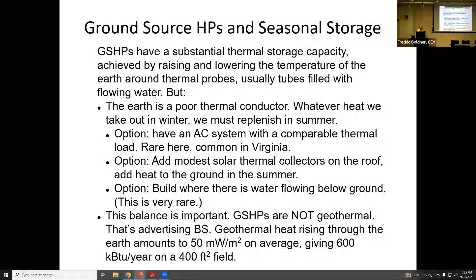Something that's very rare is to have a water table that's actually moving. But if you do, that will bring in enormous amounts of heat and take them away. So that takes care of it. But the balance is important. And one reason it's important is that there is a misnomer that's used quite often when these are called geothermal heat pumps. They are not geothermal. The total amount of heat coming up from geothermal heat is 50 milliwatts per square meter. If you've got a 400 square foot field, that's about 600 kBTU per year. That's much less than what you need in the heat pump. You're putting more down in the summer, pulling much more up in the winter. The geothermal is just sort of a sidelight.